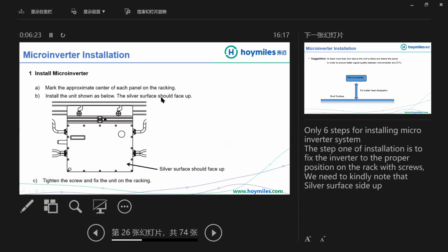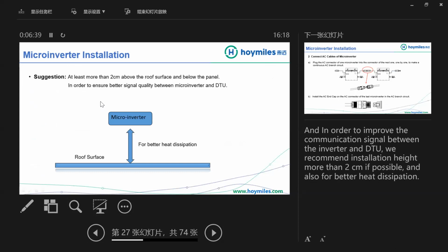The first step of the daisy chain installation is install microinverter. Mark the approximate center of each panel on the racking. Install the unit shown as below. The silver surface should face up. Then tighten the screw and fix the unit on the racking. Our suggestion is the microinverter should be at least more than 2 centimeters above the roof surface and below the panel, which in order to ensure better signal quality between the microinverter and the DTU.